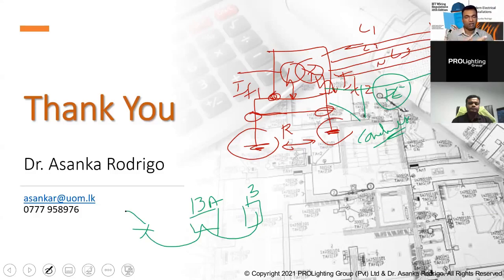socket outlet, because the other thing is the standard also says that the cable and the protective devices should be selected for the maximum demand. Otherwise you will violate that requirement also. So if it is one socket outlet and your maximum demand is 13 ampere, of course you can wire using 1.5 millimeters squared with a 10 ampere circuit breaker, but the 10 ampere will not be sufficient because then it reduces the maximum demand. That's why the standard says that if you are wiring, then 20 ampere with 2.5 millimeters squared is given as a standard requirement. I hope I have answered the question.